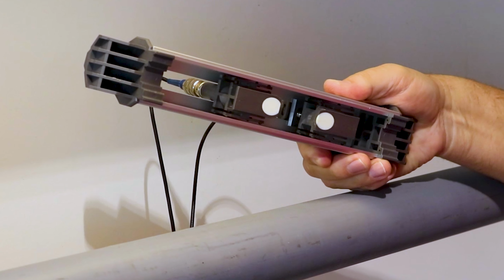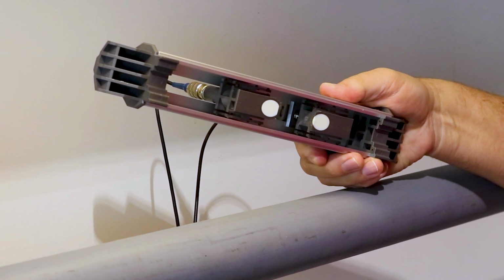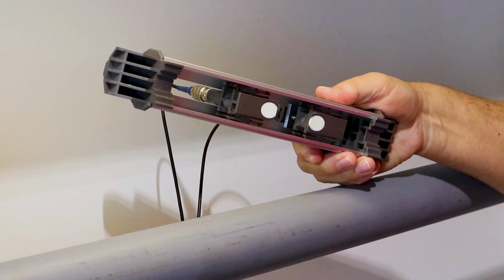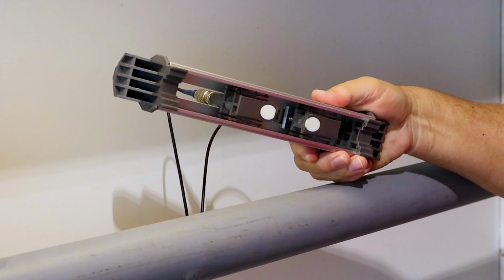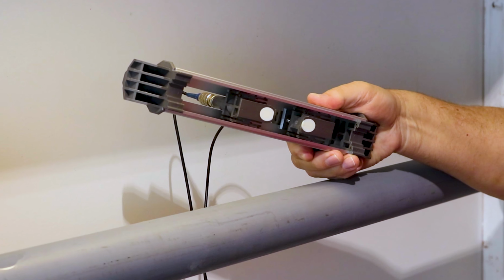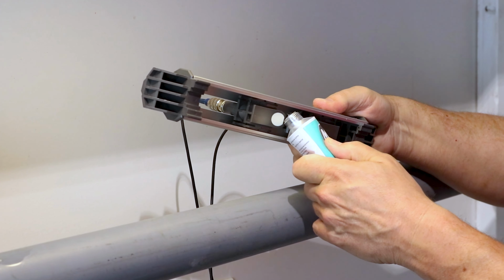Now the way this works is the flow meter transducer emits a frequency, say 1 or 2 megahertz depending upon the transducer, which is a sound we humans can't hear, and it travels through the pipe wall into the processed liquid and back again. The traditional method used to enhance this transmission of sound uses some type of acoustic conduit or pathway to send and receive our frequency.